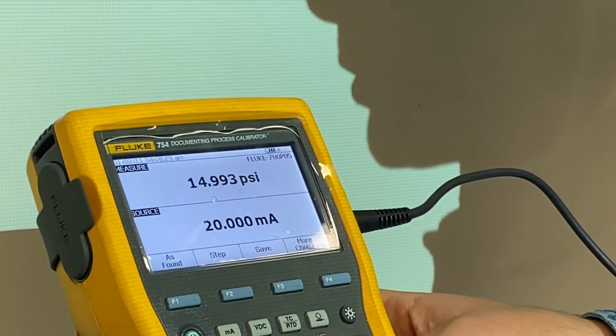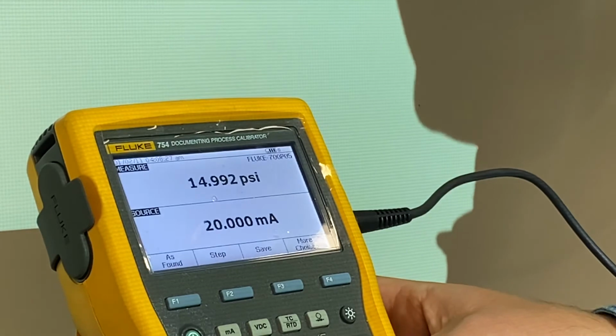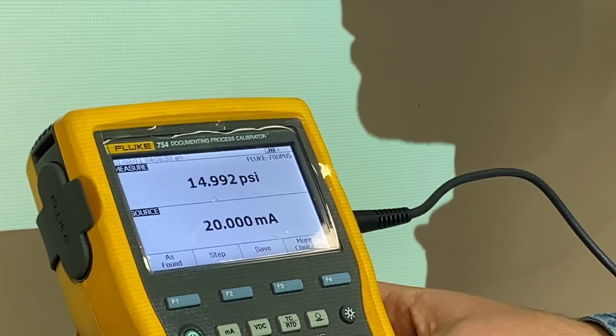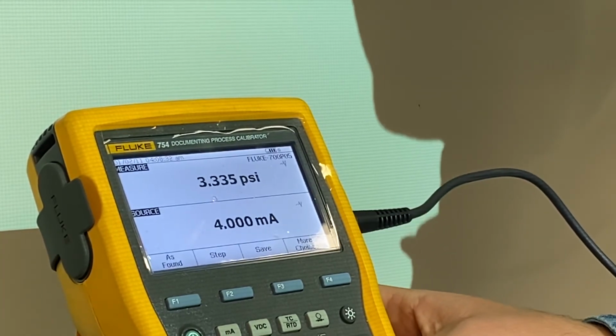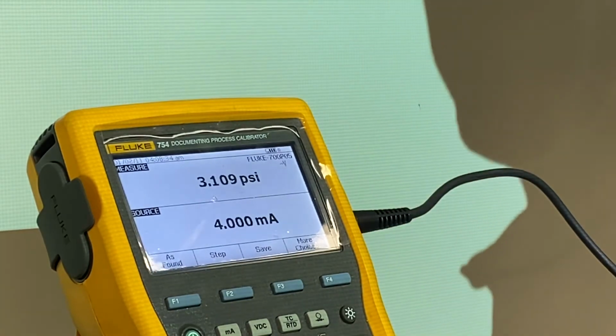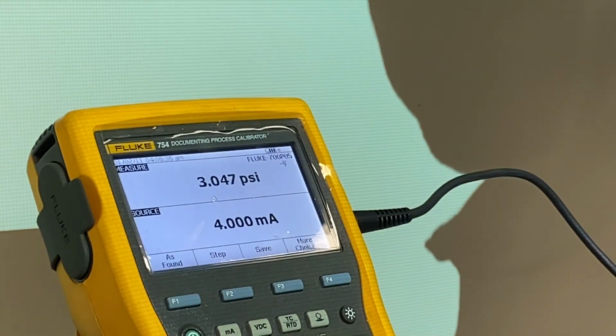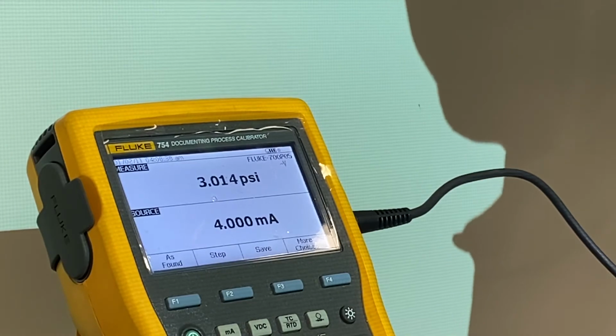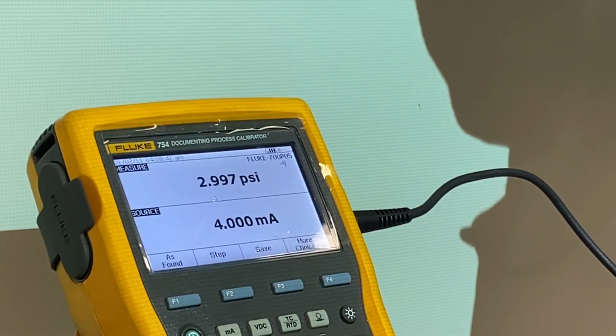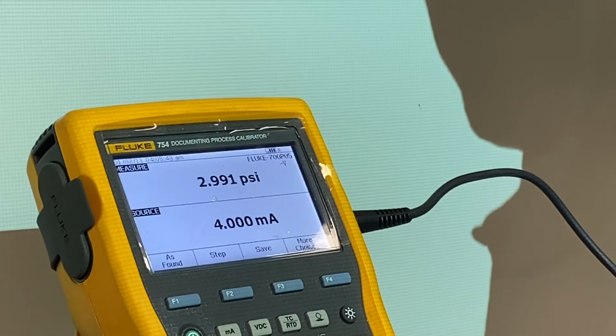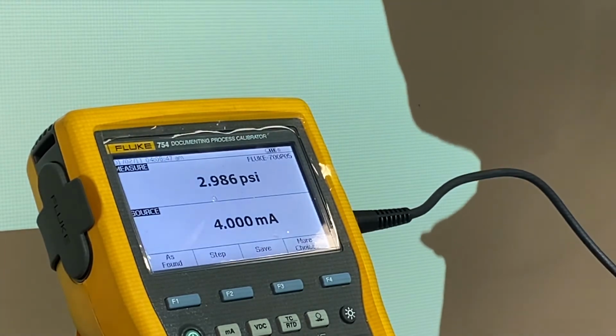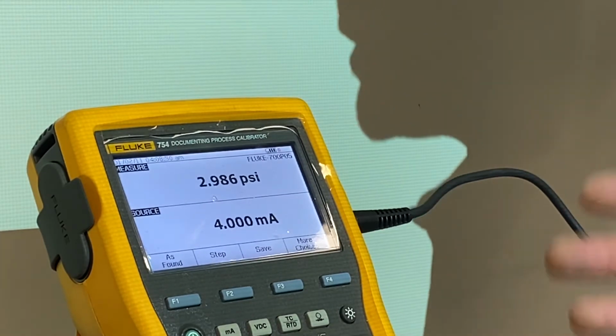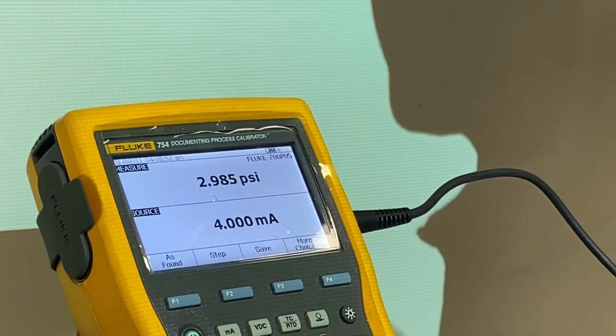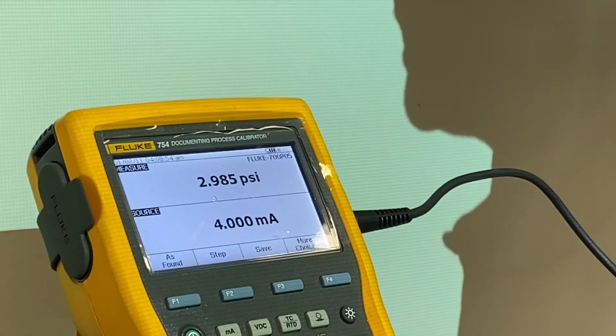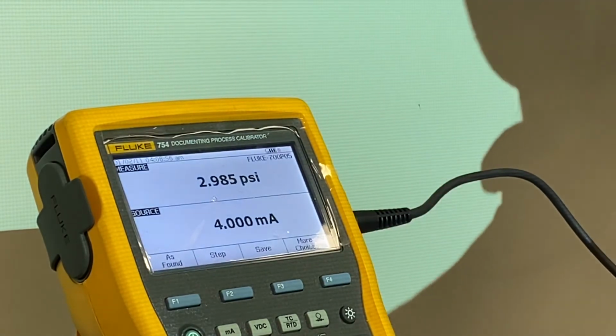So now we are going to go through our 5-point calibration check and ensure that we're good on all of our values. So starting at zero. It takes a little time for the I/P to settle, which is normal. Any facility would call this within tolerance, but us striving to the highest degree of excellence, we're going to adjust our zero again to get it even closer.